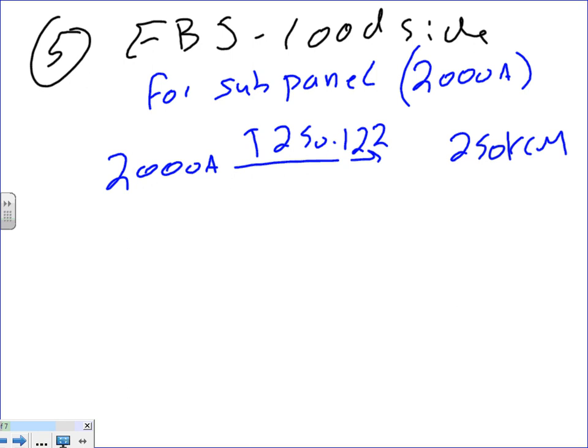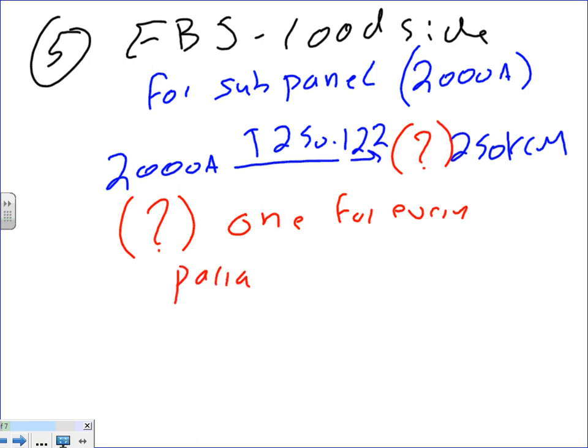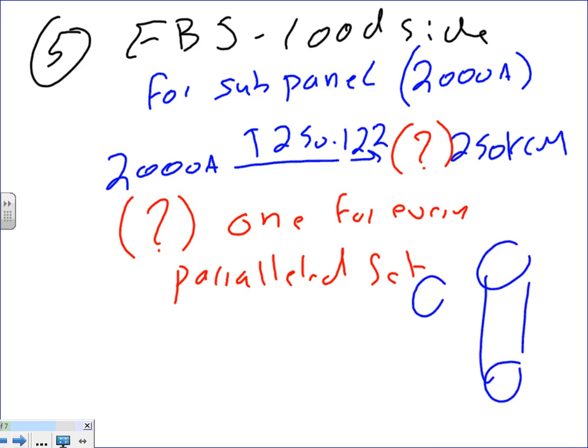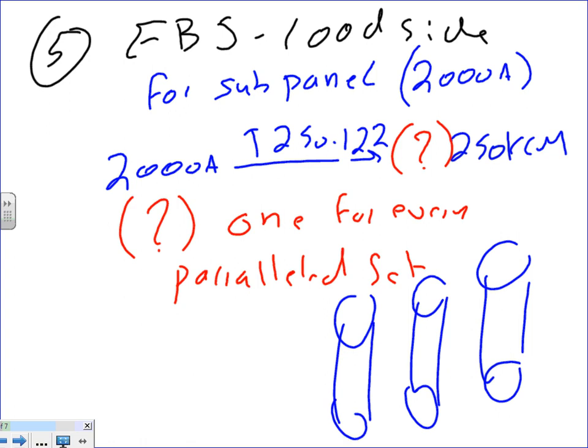Well, you're going to have 1 for every conduit that goes to that switch gear. If you parallel, you're going to put 1 in every conduit. So the question mark here means 1 for every paralleled set. If you parallel 10 sets, you have 10 of them. 1 for every parallel set. Are you guys with me here? So if I parallel 3 sets, 1, 2, 3, suppose I parallel 3 sets to carry this feeder, you need 1 here, 1 here, and 1 here. Everybody following with that one, guys?